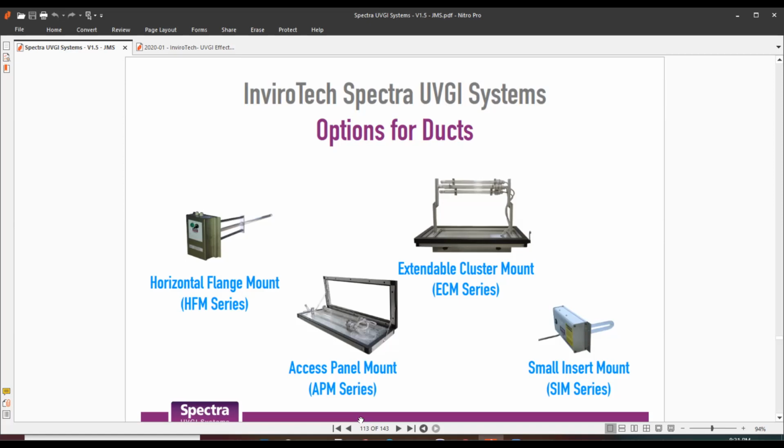Normally for UV light, you always consider the operation hours and the lamp life. So say, for example, your provider's lamp life is 10,000 hours, then the maintenance will be after 10,000 hours. That's how it works when it comes to maintenance. Do I change my lamp regardless of whether it's working or not, if it's over the estimated lamp life already? Very good question. Say your UV supplier claims their lamp life is 10,000 hours. It can still be working after 10,000 hours, but the efficiency usually drops to only 80%. So if before it was running at 100% efficiency, after 10,000 hours it's only 80%.